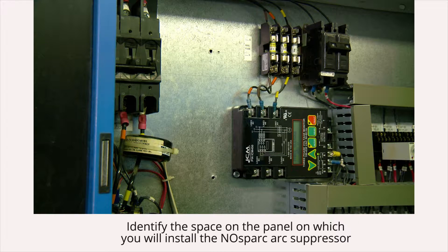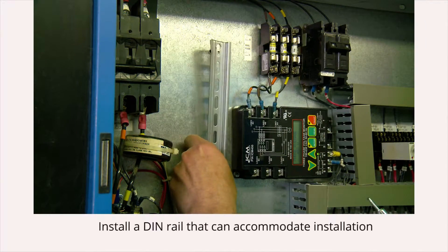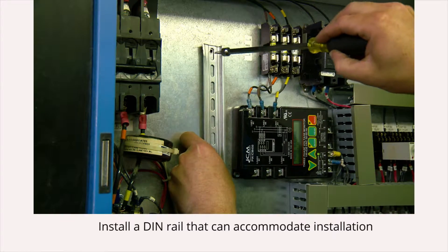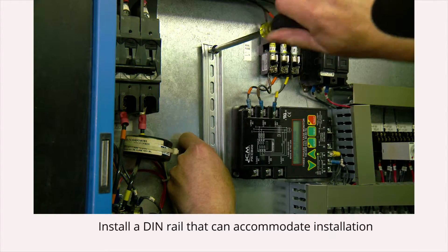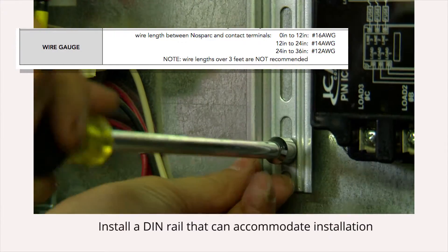To begin this installation, identify the space on the panel on which you will install the NOsparc arc suppressor. Refer to the wire gauge table in the user manual to ensure the proper wire length. Next, install a DIN rail that can accommodate the arc suppressor installation. Note that wire length should never exceed 3 feet.